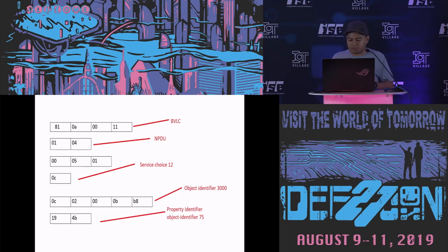configured there. So in this case, the device is using a 3,000 integer in order to execute functions. I mean, you cannot execute something without that number specified in the packet. So for example, if you try to write values there, and the value does not match this value 3000 in the device, you are not going to be able to write anything. So you need to first know this value in order to then write properly.